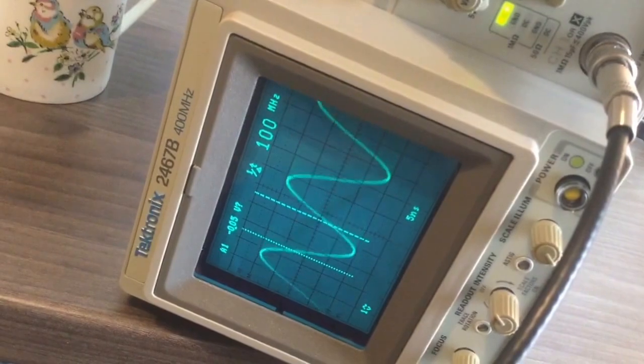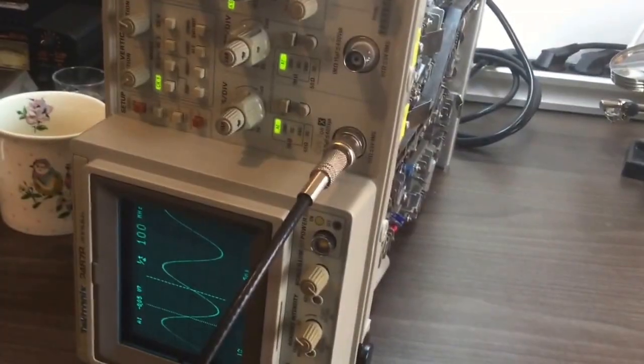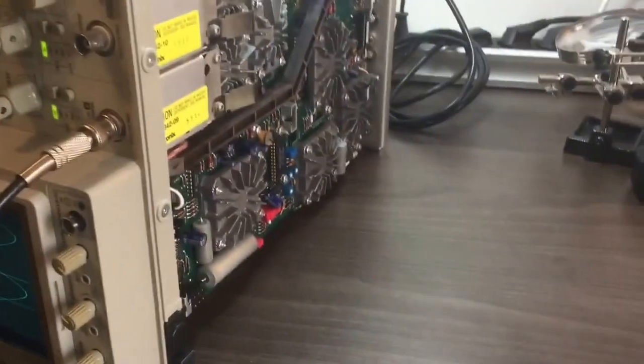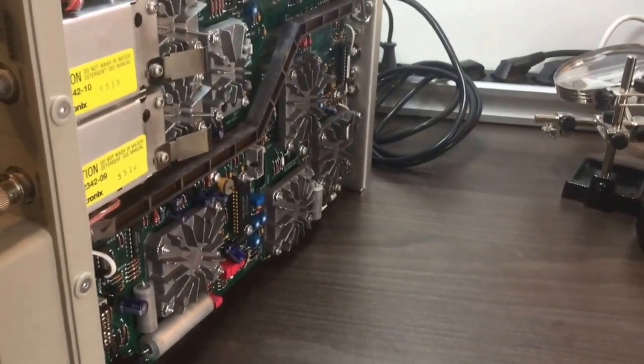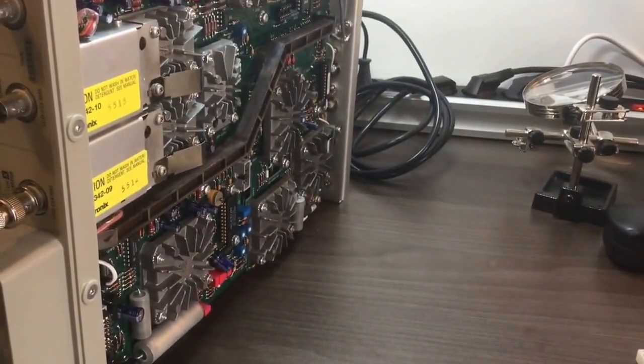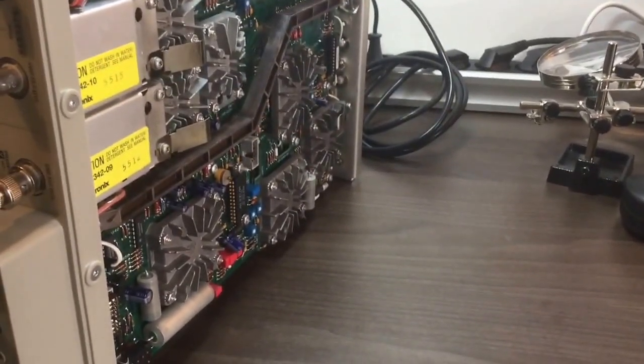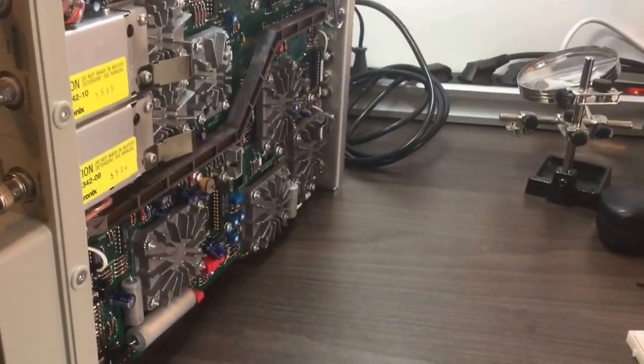To be fair, I'll wait a bit for the scope to warm up. I checked the temperature. I don't keep it on with the cover — when the scope is out of its chassis — I don't keep it on more than 5 minutes or so because I'm concerned about the heating of the hybrids here.